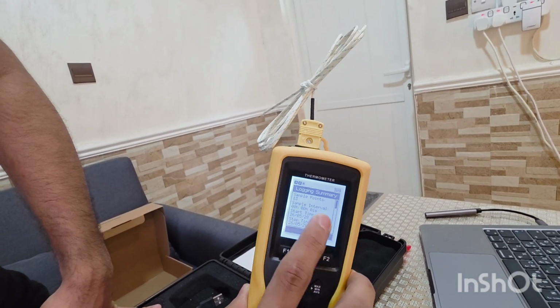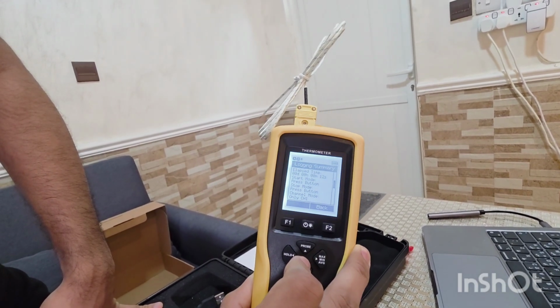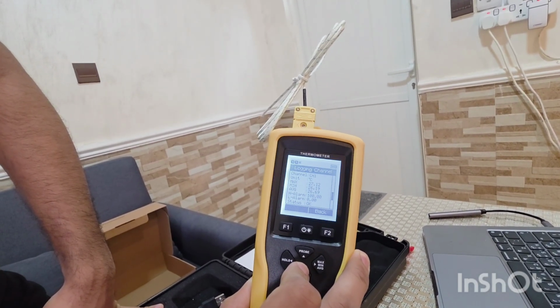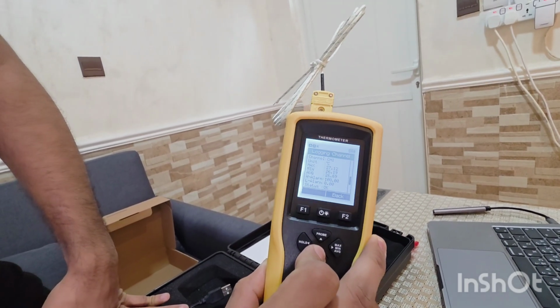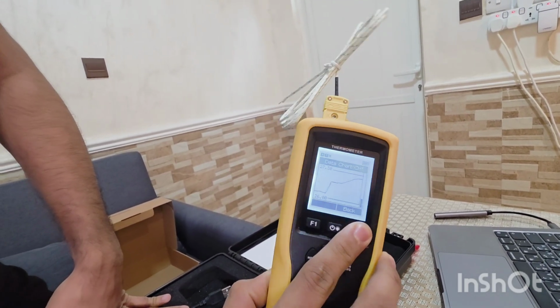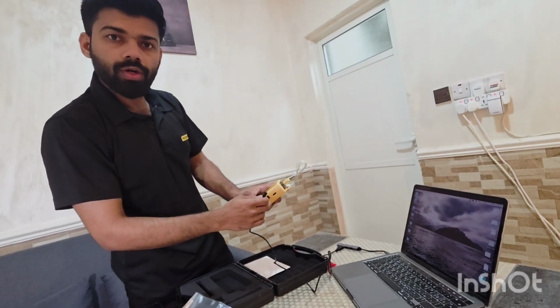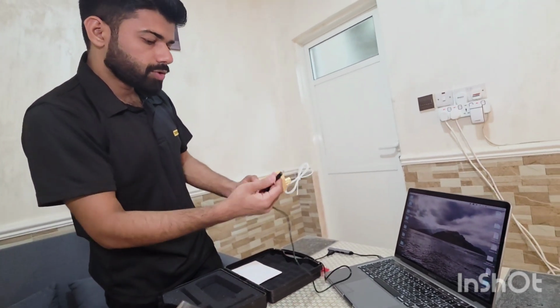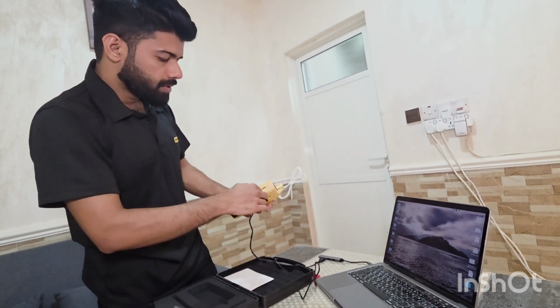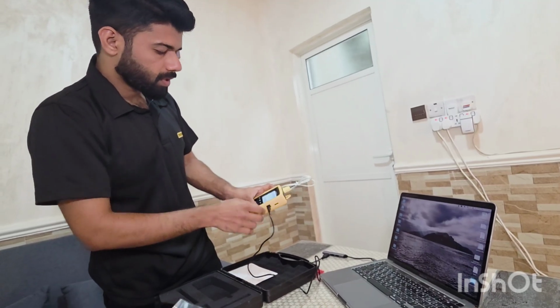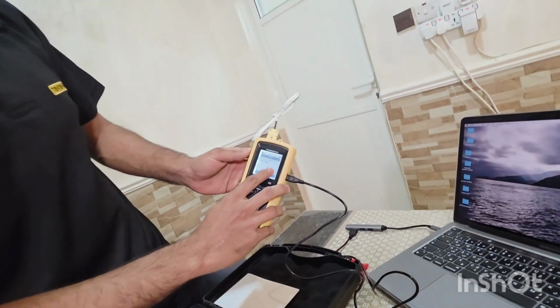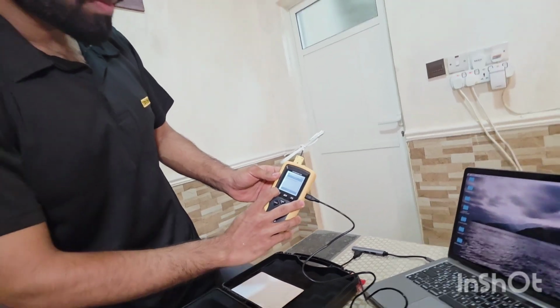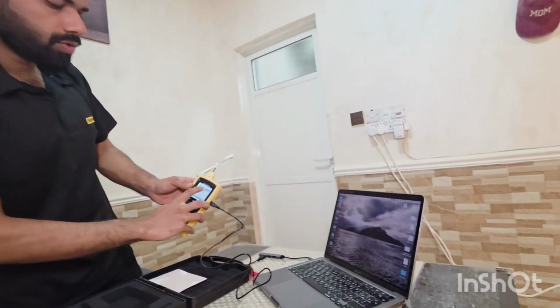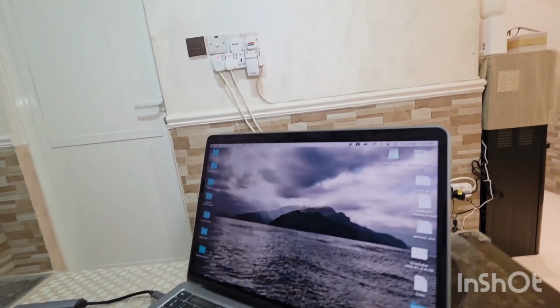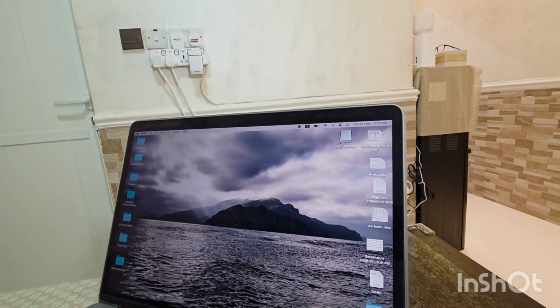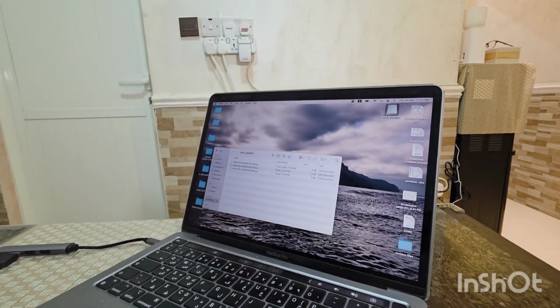More detail on the 13 sample points and so on you can see by connecting to the computer. To view the recorded file on the computer, you just need to use the USB cable provided along with the meter. Connect to the computer, and it will ask if you want to use USB. Press yes. Then it will go to USB communication mode. After that you can see the data report come up like this.